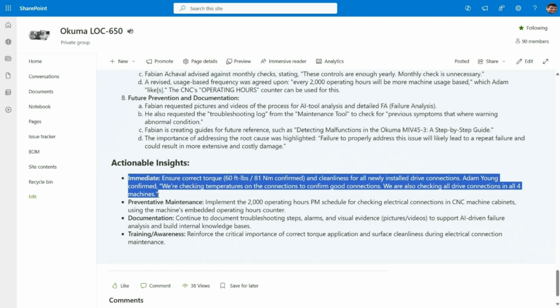Absolutely critical. Second key step: thoroughly clean surfaces. Before you make any connection, especially power connections, ensure all the contact surfaces on the terminals and on the cable lugs are impeccably clean. Use an appropriate electrical contact cleaner. Any contamination, grease, oxidation, it's just adding resistance. Clean surfaces, correct torque, based on operating hours. Those sound like the core preventative actions right there.